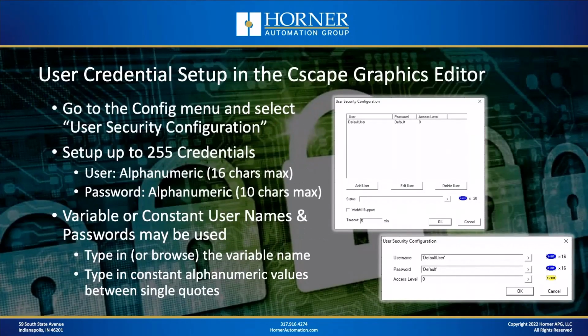The other thing you're going to need to do in terms of Cscape setup is set up user credentials. That's done from the Cscape graphics editor. You go to the config menu in the graphics editor and you'll find user security configuration. That's where you can plug in up to 255 sets of credentials. Each credential consists of a username, up to 16 characters, and a password, up to 10 characters. You can type them in either as a constant, in other words a fixed username and fixed password, by typing the data in between single quotes, or you can type in variable names instead, and then those credentials will be pulled from those particular variables.